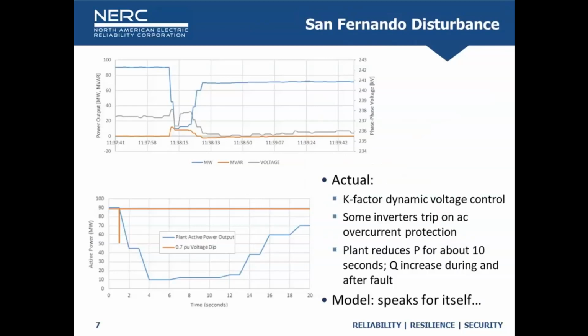Here's another example. This facility has explicitly told us they do not use momentary cessation. They've got newer inverters, they use K-factor dynamic voltage control for those inverters. A couple inverters tripped on AC overcurrent protection in this case, so we can ignore the reductions. Here, for example, in the top plot, you can see pre-disturbance at about 90 megawatts, post-disturbance at about 70 megawatts.